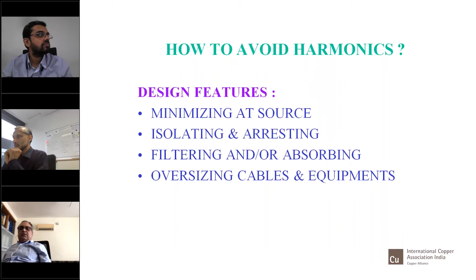Proper specifications and selection of equipment is the most important thing. The UPS I was talking about, and VFDs: we must ensure that these UPSs give you less than 5% current harmonics on the input side, and a power factor higher than 0.95 on the input side.